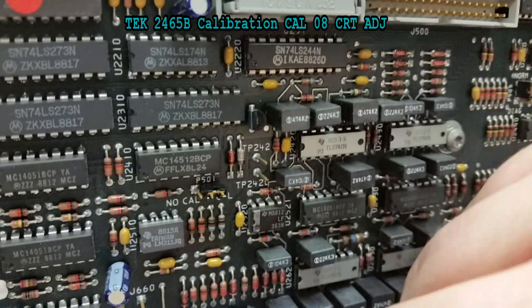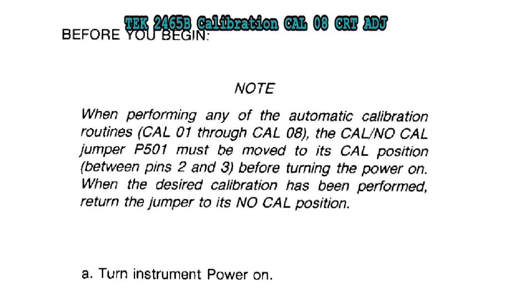One thing it does tell you is that when you've completed the procedures, to move it to the no Cal position. What it doesn't tell you right here is that you have to turn the power off and then move the jumper before you turn the scope back on. It doesn't tell you in the Tektronix manual, but it does tell you in the Army manual.